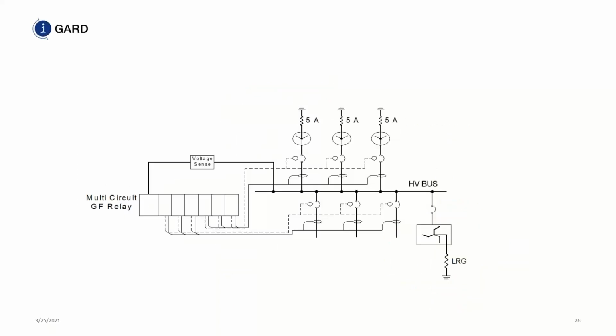Same thing for medium voltage generators. If you have 5 kV or 15 kV, you can actually employ resistance grounding, not necessarily high, but maybe a low resistance grounding system on the bus, limit the fault current, and then continue.